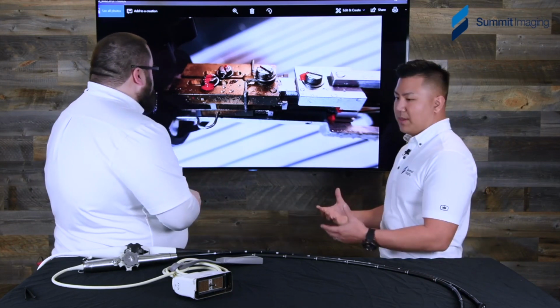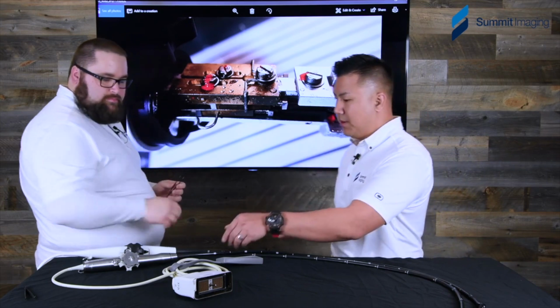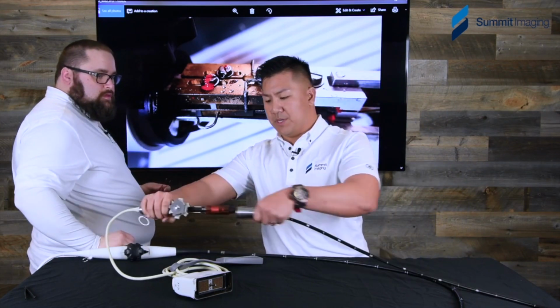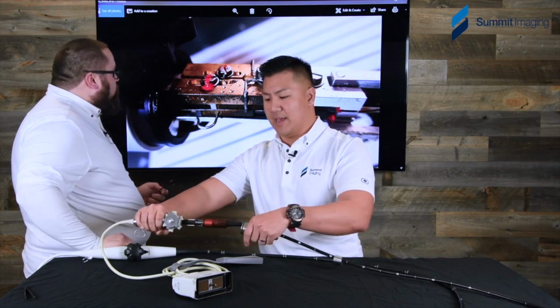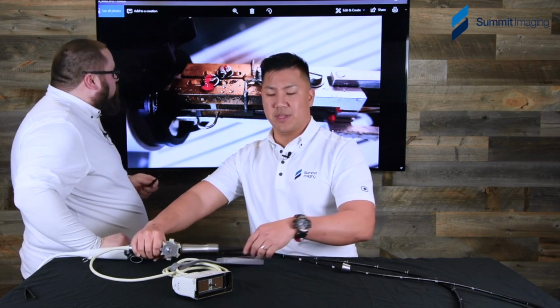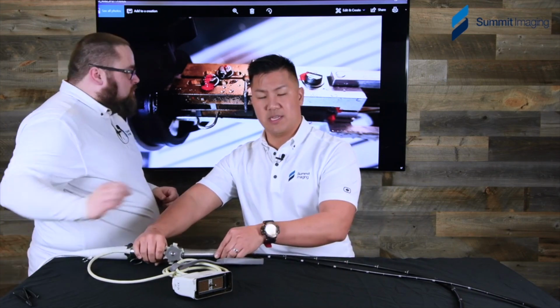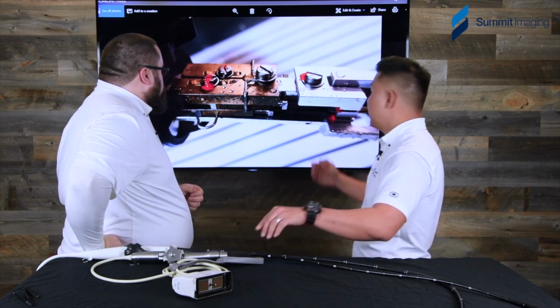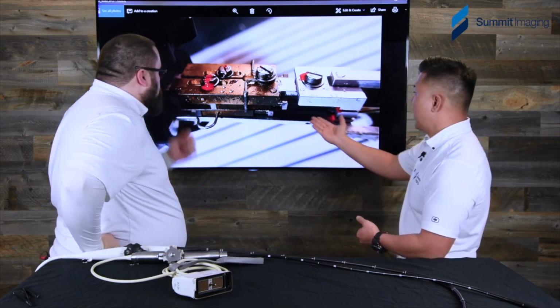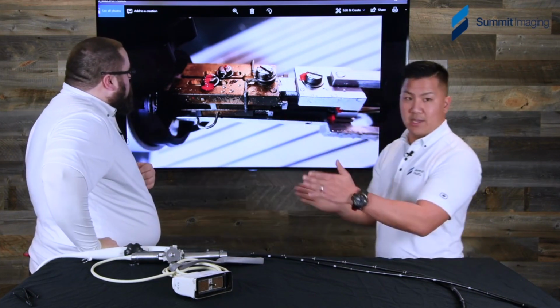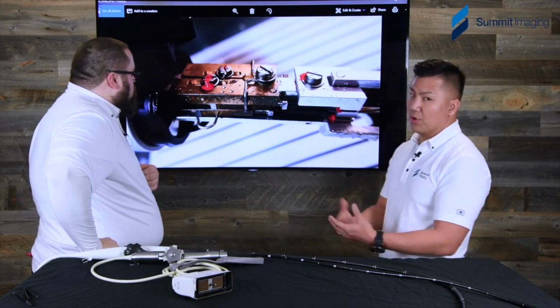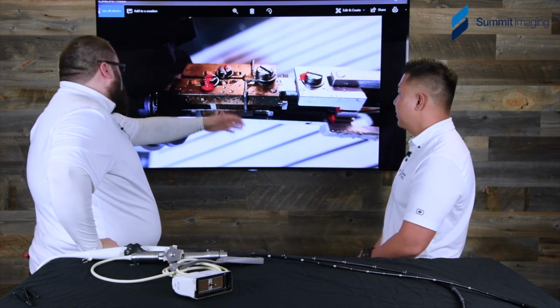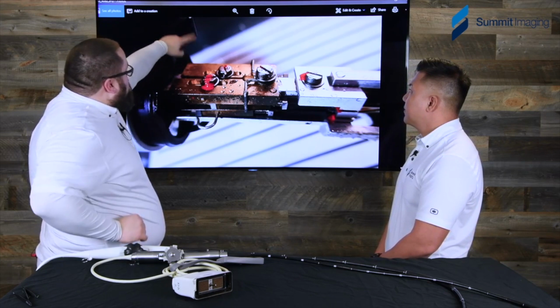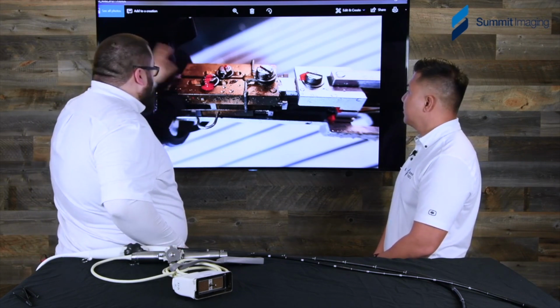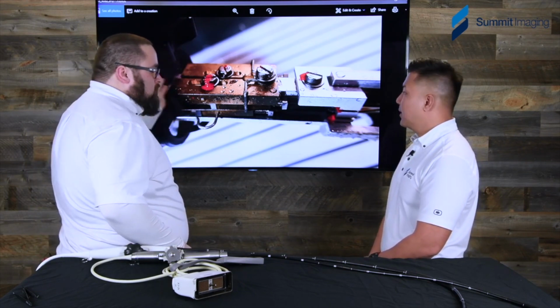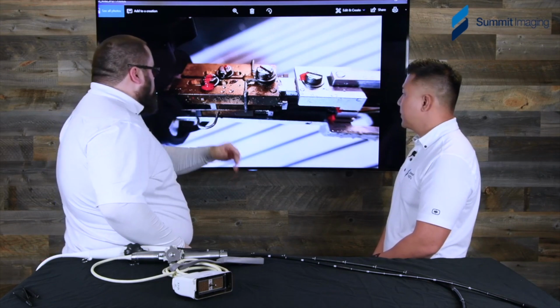So to give some context, this photo here is when you open up the TEE probe handle. We're looking at the inside now. This is fluid that got beyond the metal casing and the O-rings, and now it's appearing here on the internals that actually move and articulate the lines to get these Omni probes to move where they need to. Well, and on the other side of the connector, you can actually see a bit of the knob right here. On the other side is our line splices, our bridges to go down to the head.